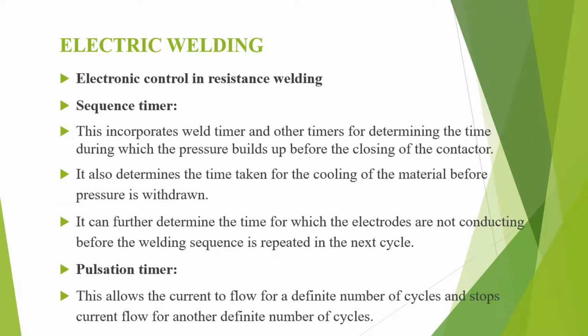transformer. Sequence timer. This incorporates weld timer and other timers to determine the time during which the pressure builds up before the closing of the contactor. This is known as squeeze time.